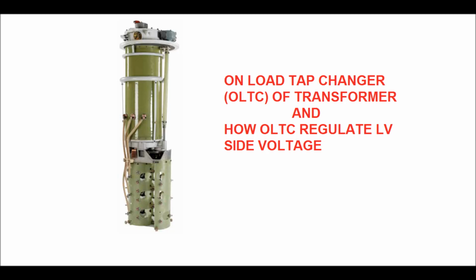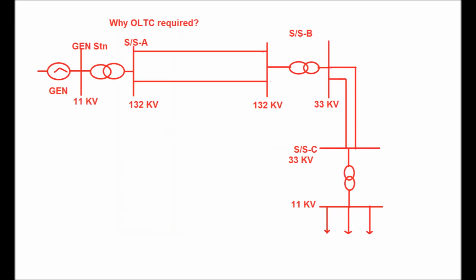Hello friends, today I will discuss the on-load tap changer, or OLTC, of a transformer, and how by changing the tap position the LV side voltage can be regulated. In this diagram, a single line diagram has been shown of how the power is transmitted from the generating end station to the distribution end substation.